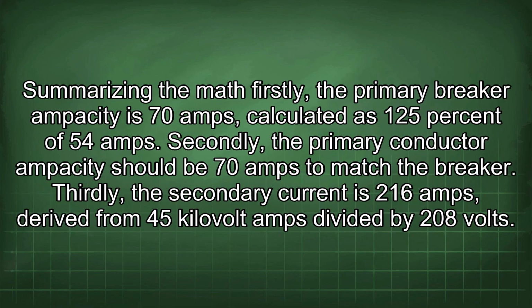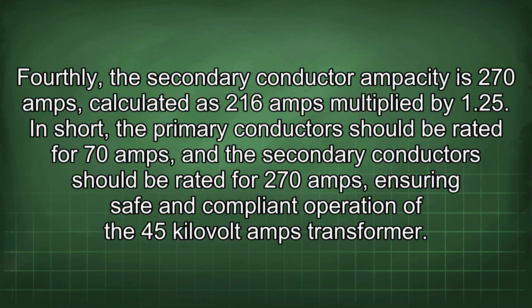Summarizing the math, firstly, the primary breaker ampacity is 70 amps, calculated as 125% of 54 amps. Secondly, the primary conductor ampacity should be 70 amps to match the breaker. Thirdly, the secondary current is 216 amps, derived from 45 kilovolt amps divided by 208 volts. Fourthly, the secondary conductor ampacity is 270 amps, calculated as 216 amps multiplied by 1.25. In short, the primary conductor should be rated for 70 amps, and the secondary conductor should be rated for 270 amps, ensuring safe and compliant operation of the 45 kilovolt amps transformer.